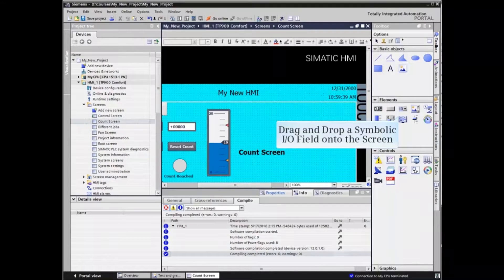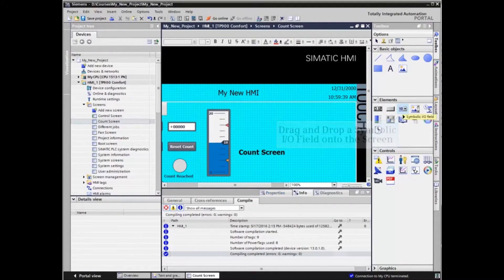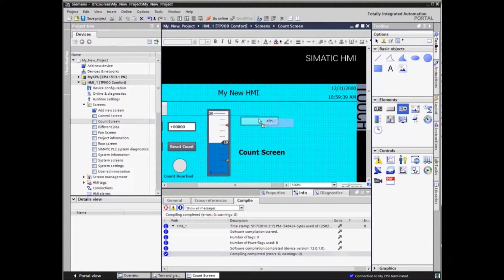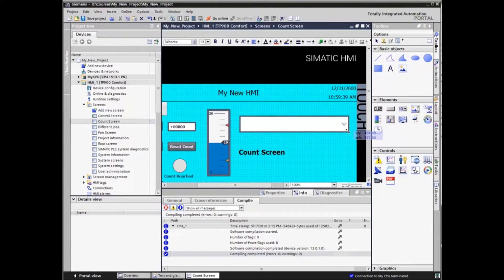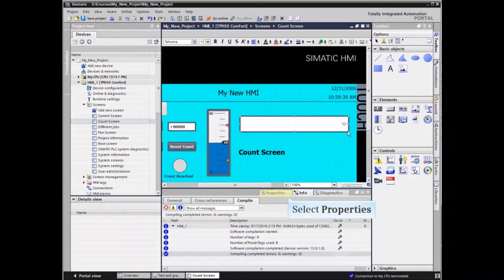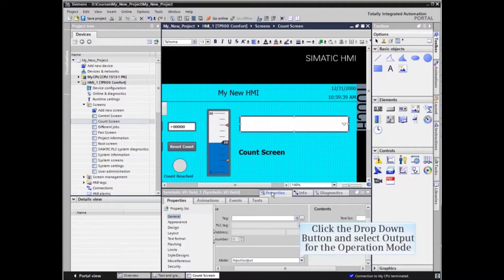Drag and drop a symbolic I/O field onto the screen and resize as necessary. With the element highlighted, select the properties tab in the configuration area and change the mode of operation as required for the application.